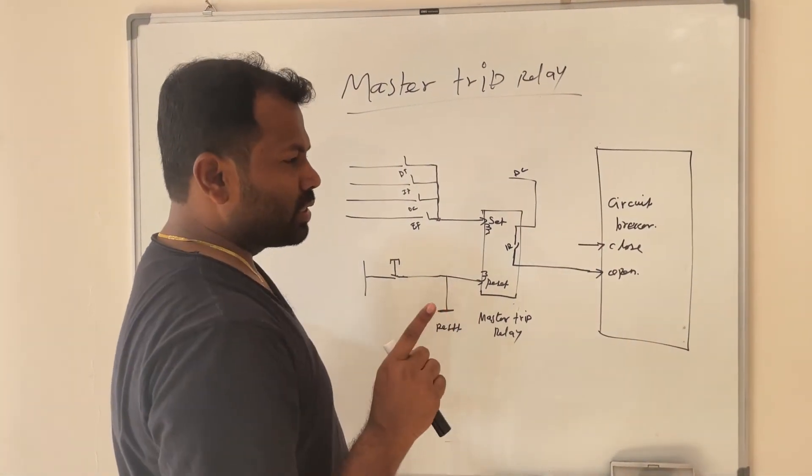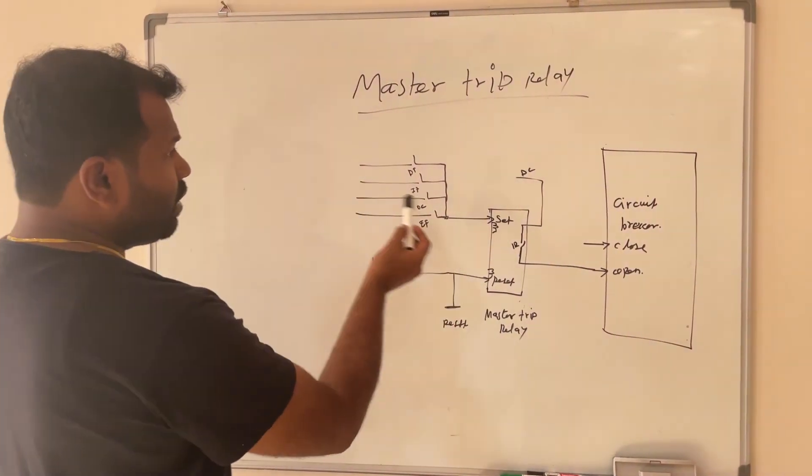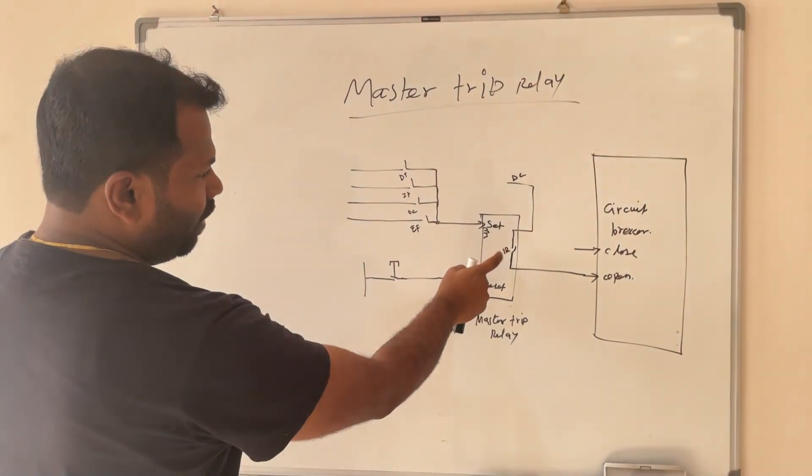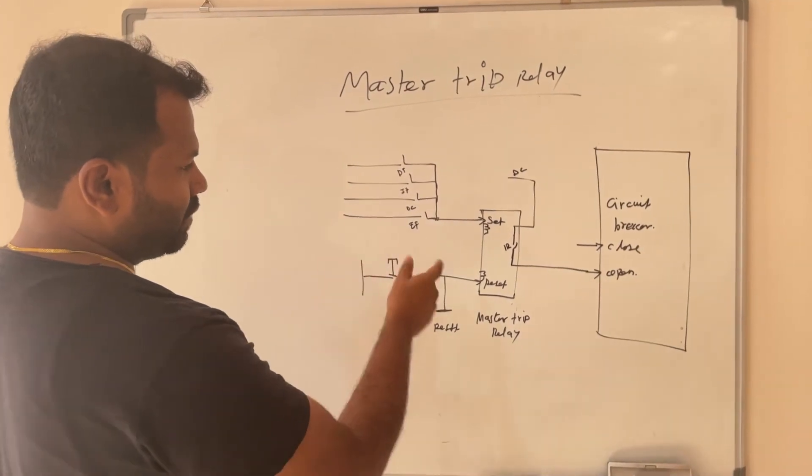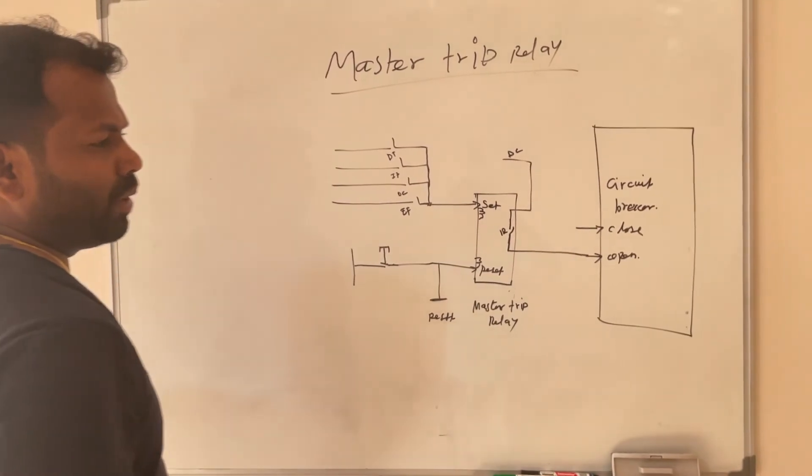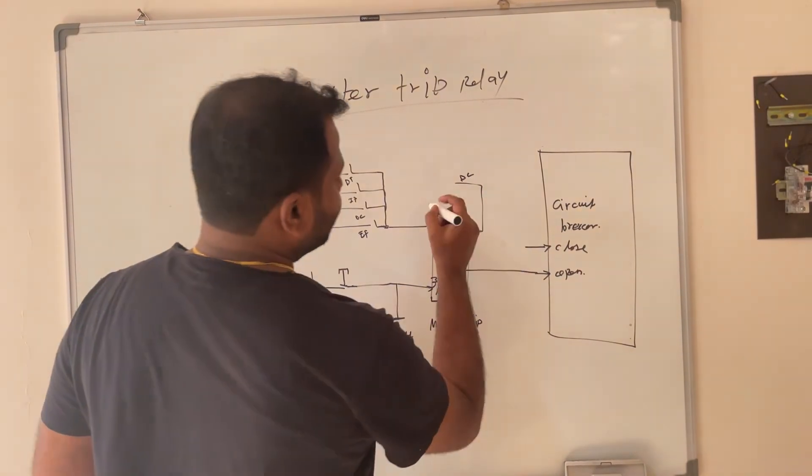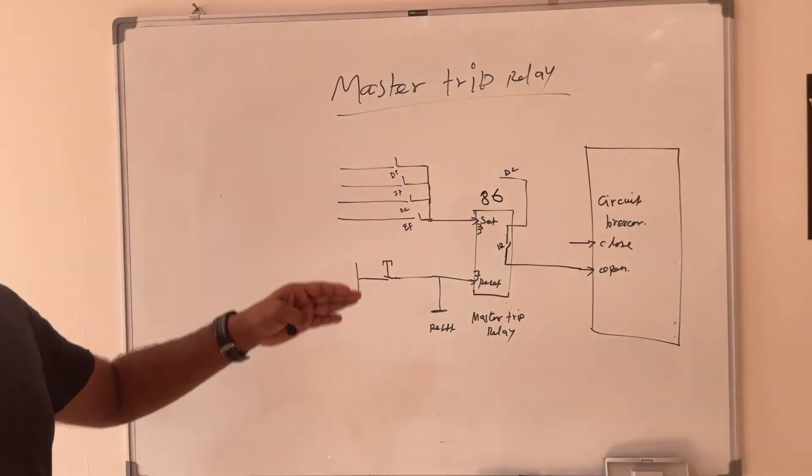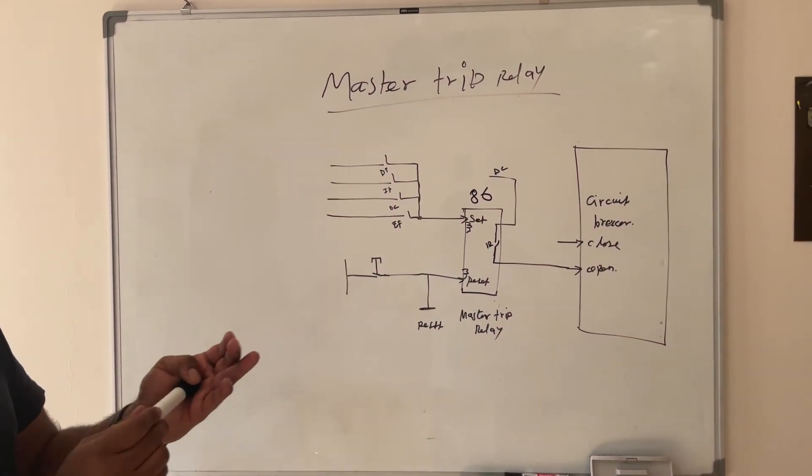From any external protection relay, this is the only one relay that will receive the fault command or trip signal, and this will decide to open or trip the breaker. That is called master trip relay and this ANSI code is 86. This is the most used relay in major substations.